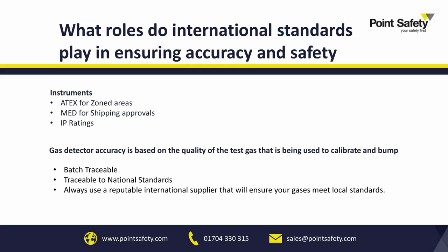Again, there are MED shipping approvals for certain meters if you're involved in the shipping market, which is like the little ship's wheel on the back of that instrument. That'll demonstrate that the meter has been approved for shipping and marine applications. All instruments will have an IP rating, normally IP 65, 66 and above, for water ingress.